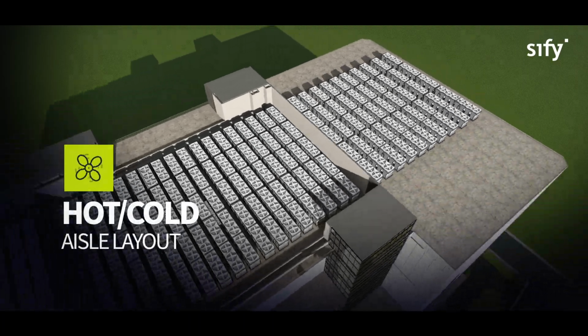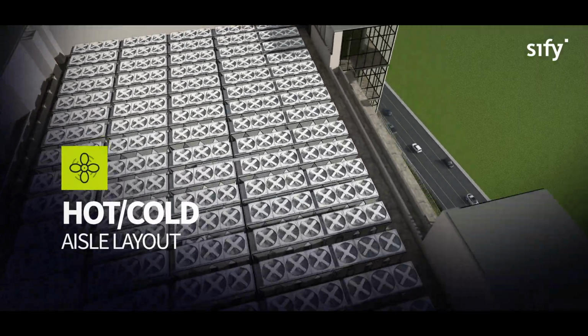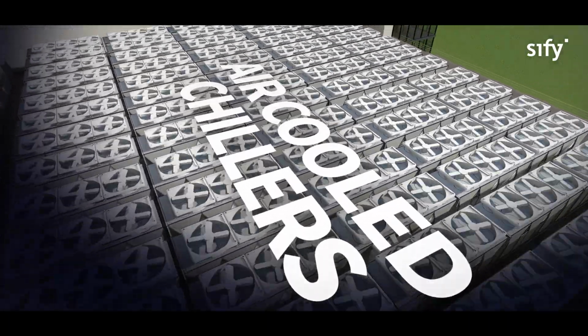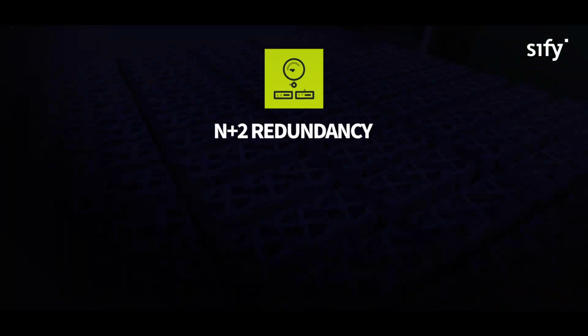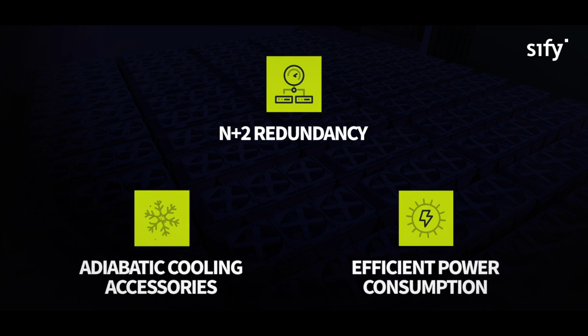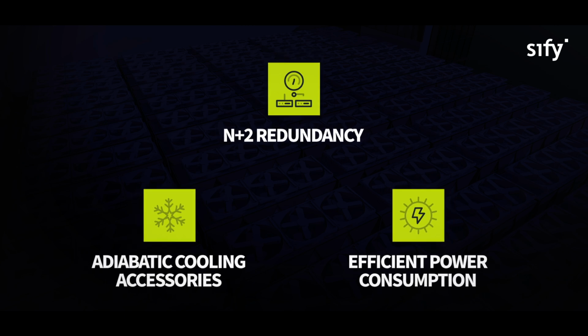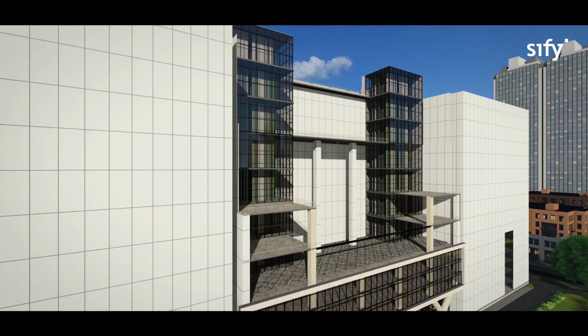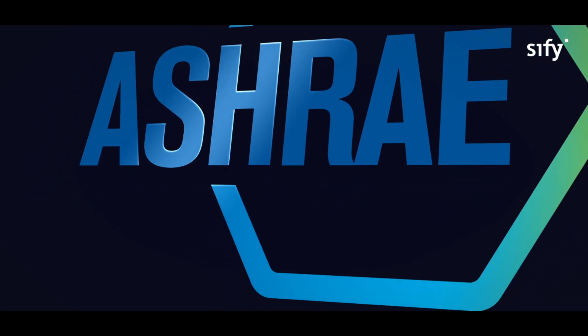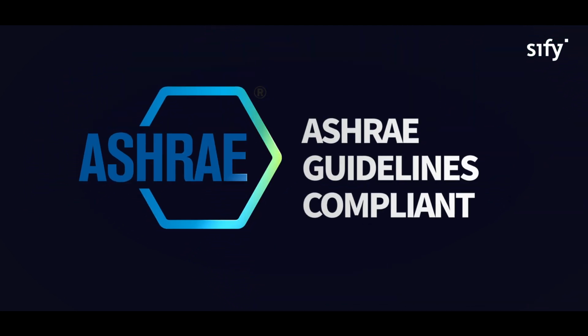The racks follow a hot and cold aisle layout, utilizing air-cooled chillers placed at the top of the facility with N+2 redundancy and adiabatic cooling accessories for efficient power consumption. The campus design complies with ASHRAE guidelines for precise temperature and humidity control.